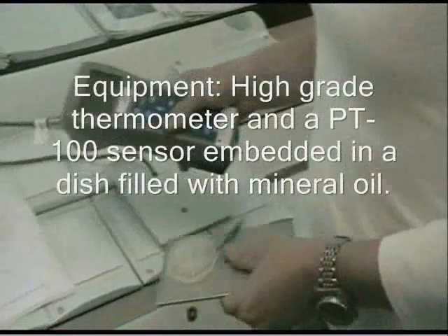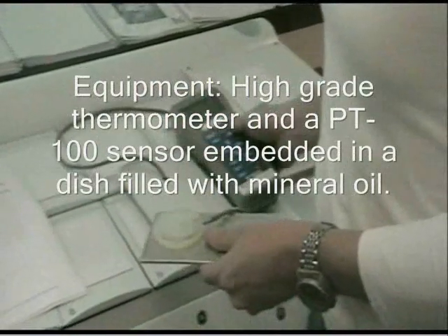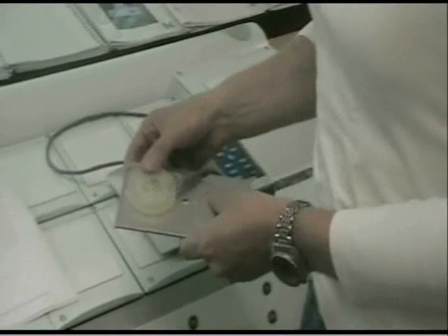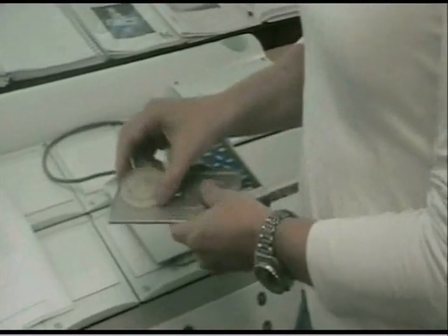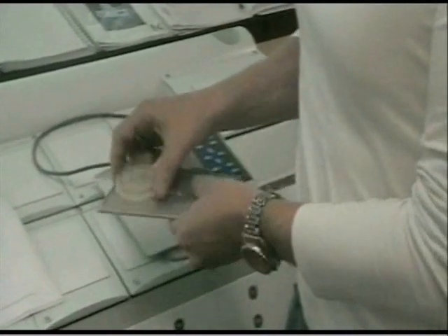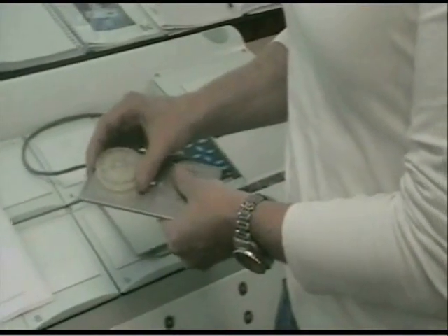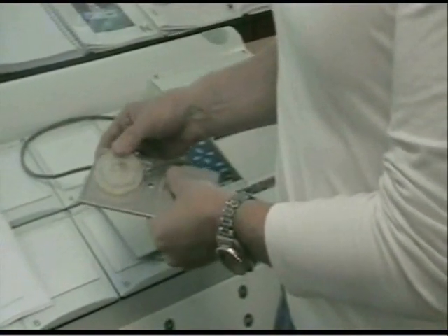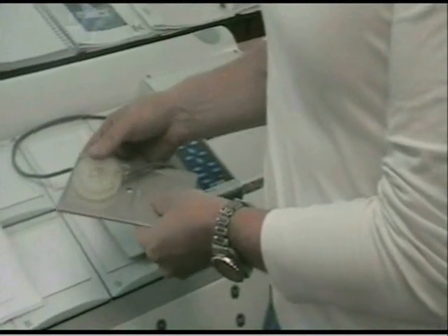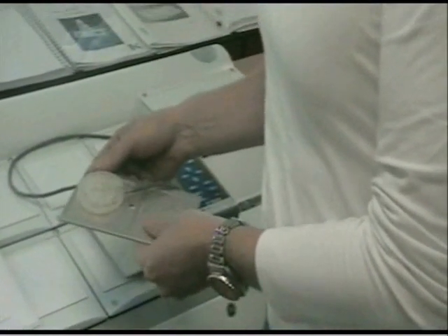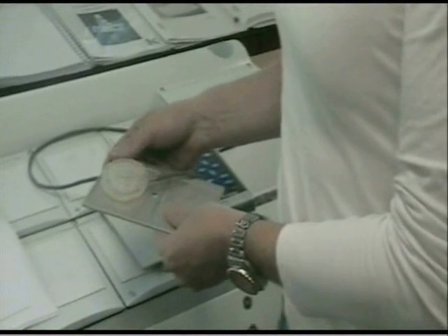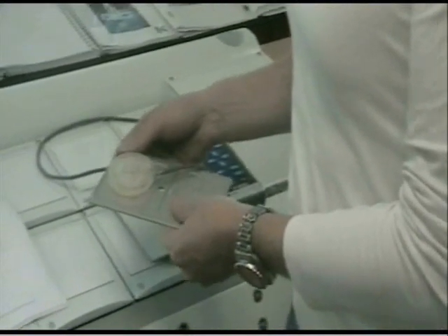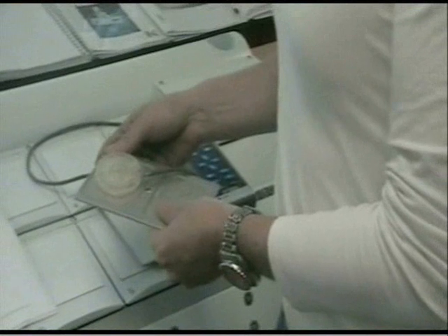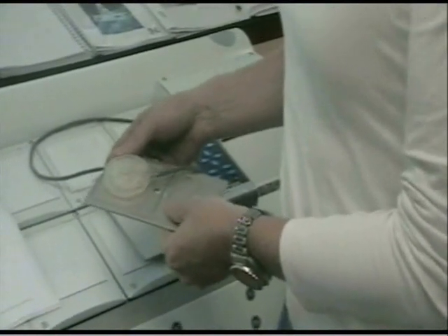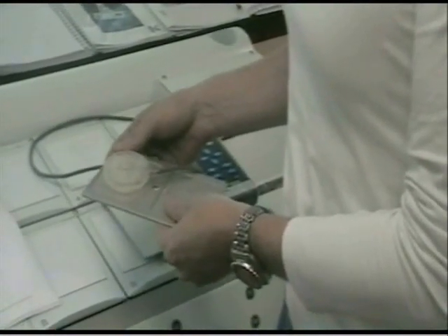To do calibration, you need a high-grade thermometer, and you need a dish like this with an embedded PT100 sensor inside it. The dish is glued to the metal insert in order to make sure that it doesn't move around during the calibration. This is something that we manufacture at K-Systems, so you can order it from us. You need it to make sure that the calibration is done without the uncertainties that would arise from gluing or trying to tape the sensor inside the compartment and having the wires coming out.